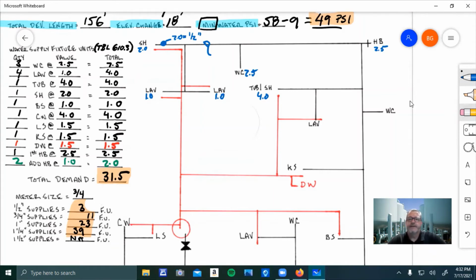Well, if I had two fixture units here, one here, which makes this one 2, this total would be 4. 4 fixture units is going to give me a total size of 3/4, right? Because like I said, down here at the bottom, it says 3 fixture units total for 1/2 inch. So the next one up, which goes up to 11, that's 3/4. So right here, that's 3/4.